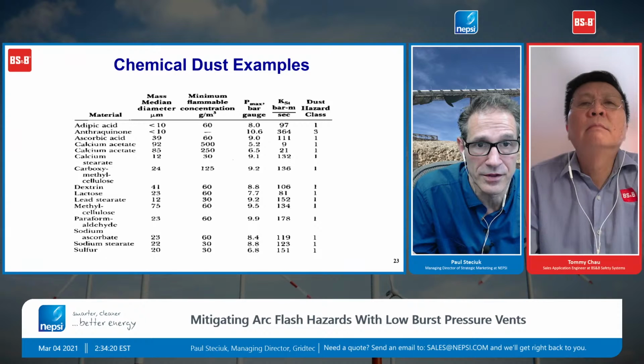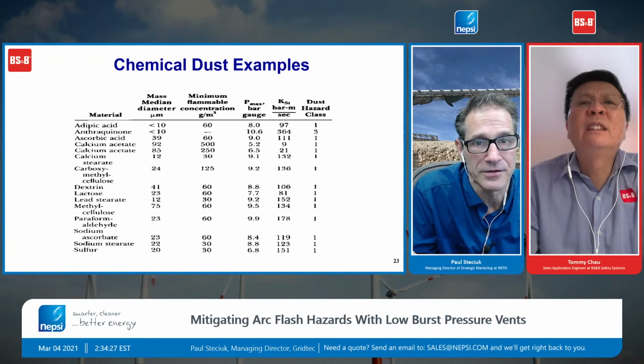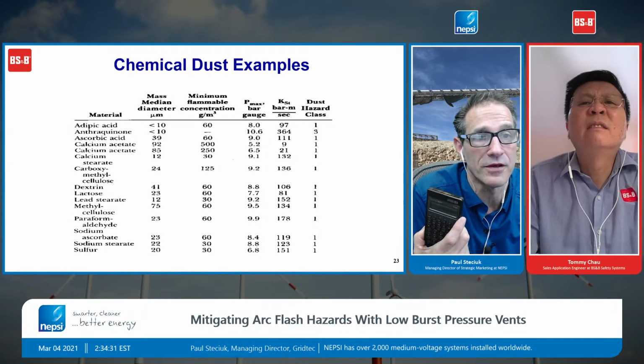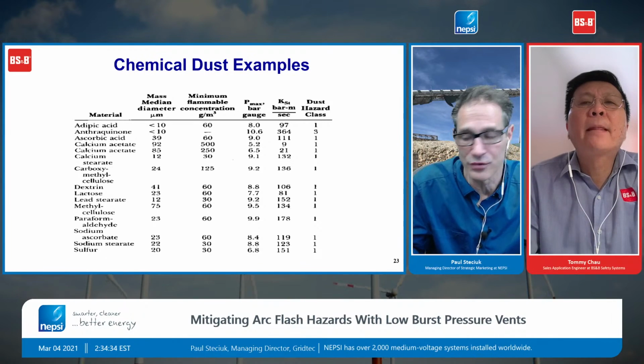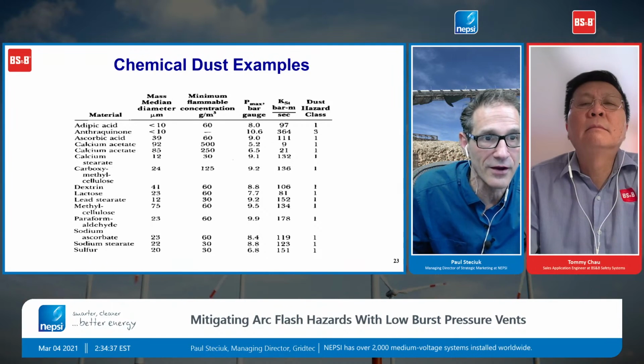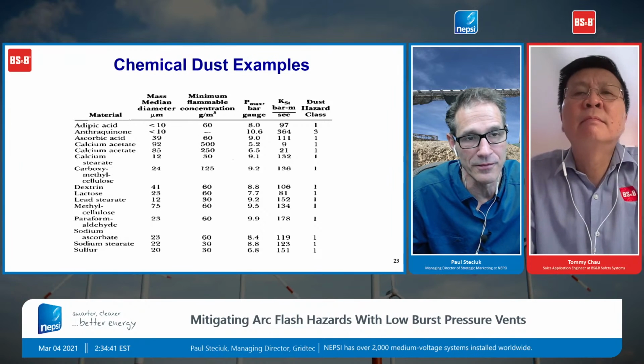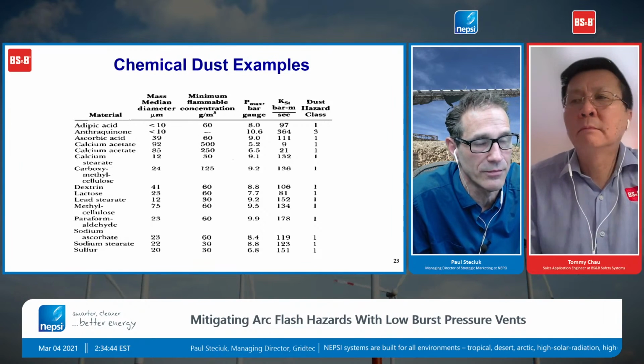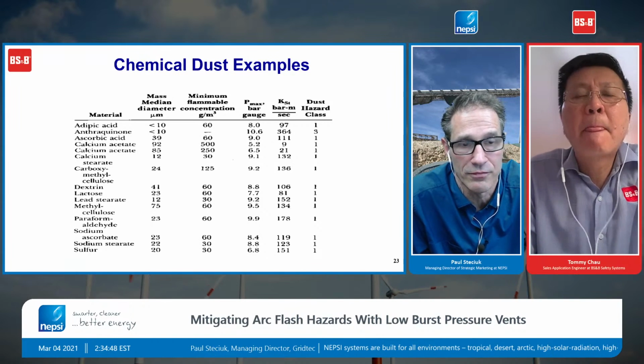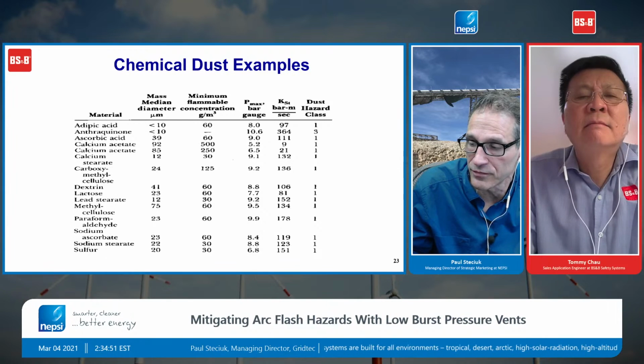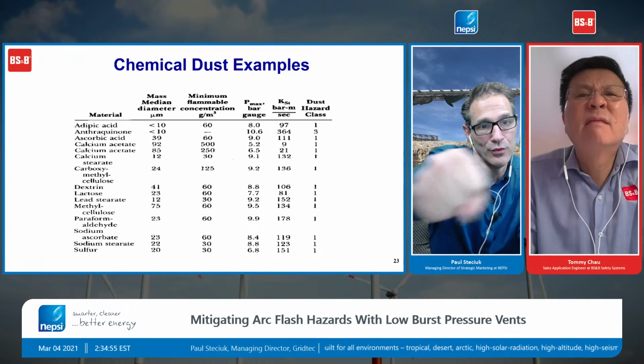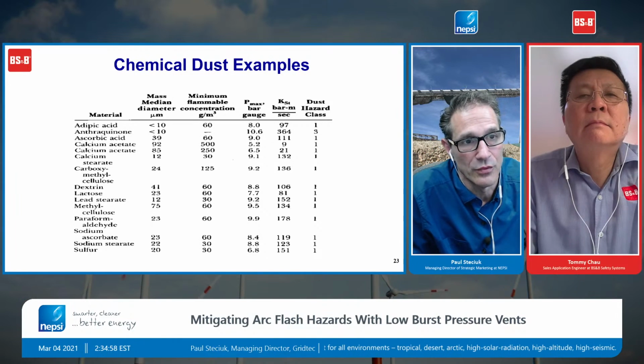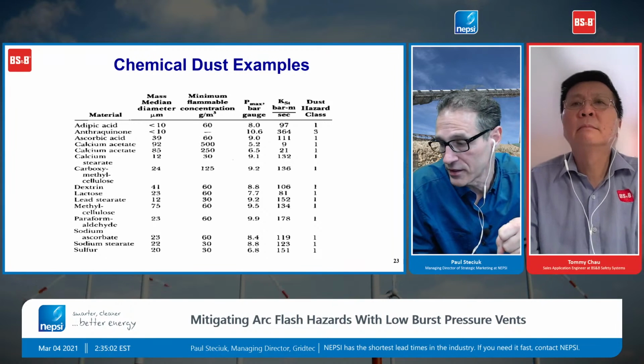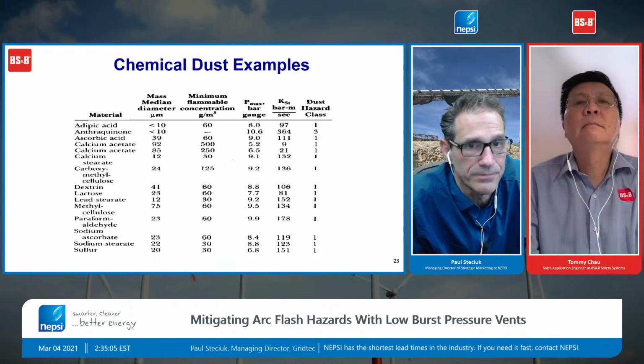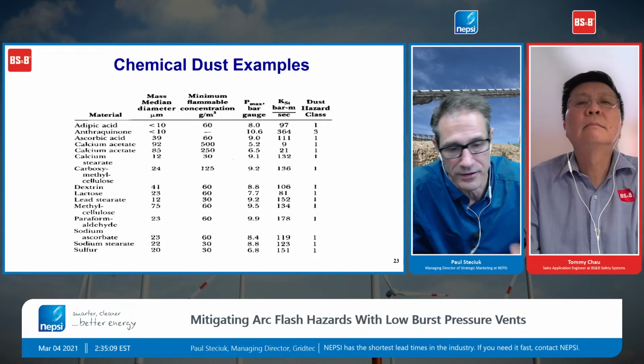You have pressure buildup. You say bars, right? Well, Pmax is in bar, not per square inch. Okay, so here I'm doing this calculation. So 4,600 square inches on a typical enclosure door, and if it's just even 1 psi, that's 4,600 pounds on a door. That's the point. We have our burst vents set at 0.5 psi, a very low value, because at 0.5 that would be about 2,000 pounds of pressure wanting to pull the door off the enclosure. So we have to reinforce our doors to prevent that 2,000 pound force from pulling the door off the enclosure. That's the most basic premise behind the design.